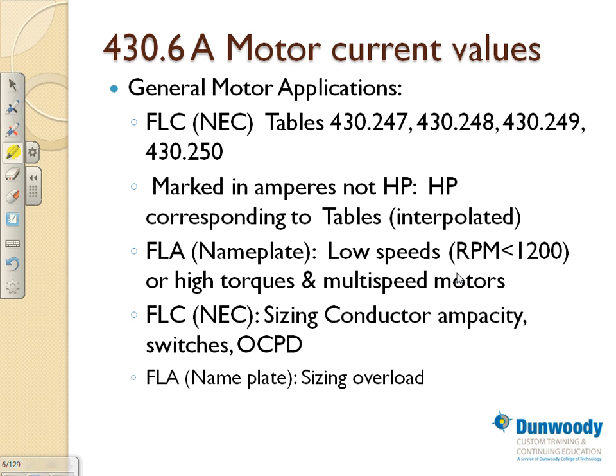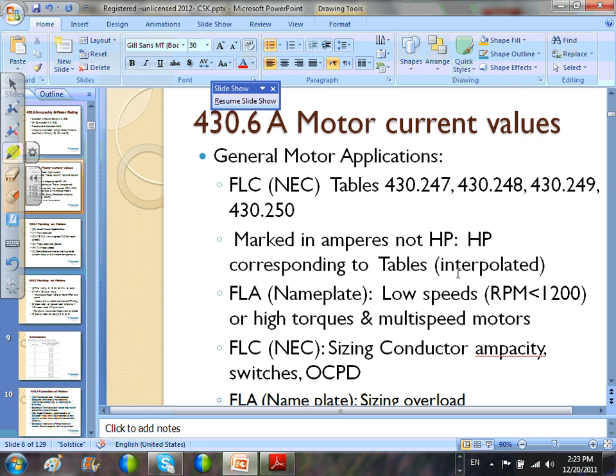Remember that 100 amp motor that I told you? Where did they come up with the 100? Where did I come up with the 100? Well, almost all the time, they're rated in horsepower. You're going to go to the NEC code and find the equivalent of the horsepower in amps. I like to go to the three-phase table 430.250, guys, and give you one very quick example, and I'll come back.